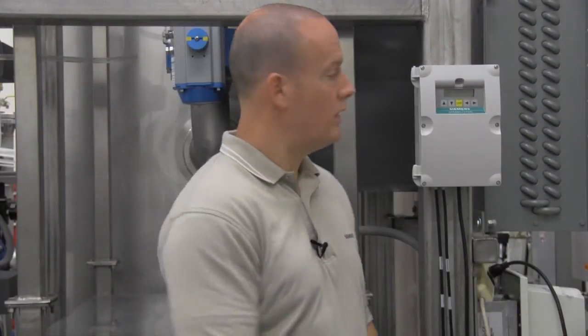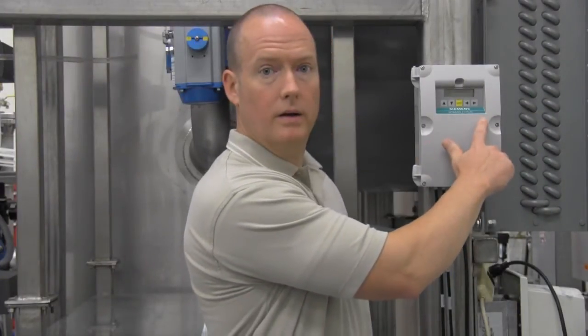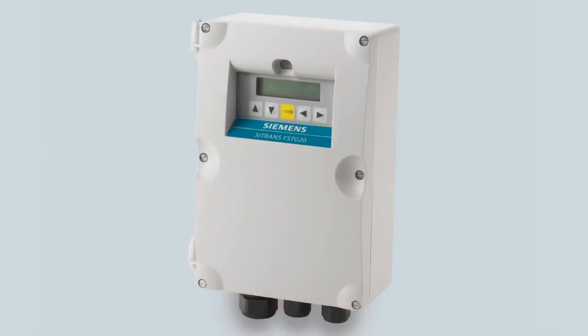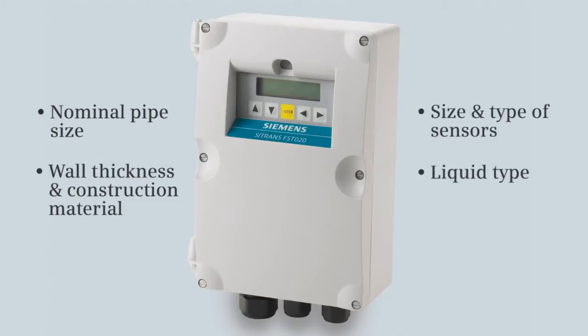For this exercise, we will program the meter using the keypad. To configure the FST020, we need the following application details: the nominal pipe size, wall thickness and construction material at the sensor location, the size and type of sensors we will be using, and the type of liquid we will be measuring. We only need to set four parameters to start measuring flow.